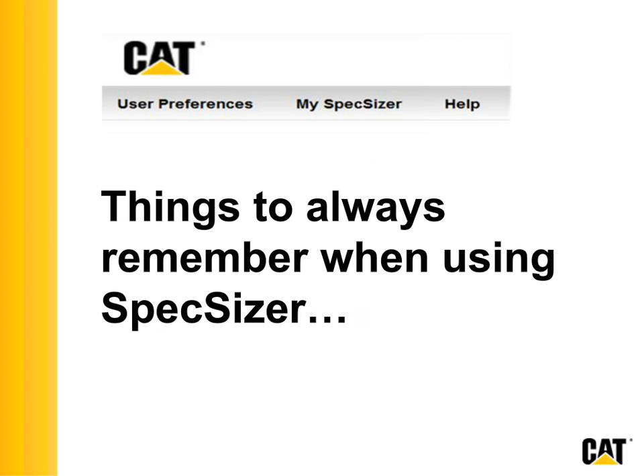The optimizer will look at your load scenario, and it will group your loads largest to smallest voltage dip groups, and within those loads, sequence your loads largest to smallest SKVA. So there's a couple things that you need to do with respect to your add loads page. Multiple load steps, pay attention to your load step sequencing, and then that last thing is the optimizer. Just always at least check it out. Even if you decide you don't want to rearrange your loads, at least always check out the optimizer and see what is the best opportunity.